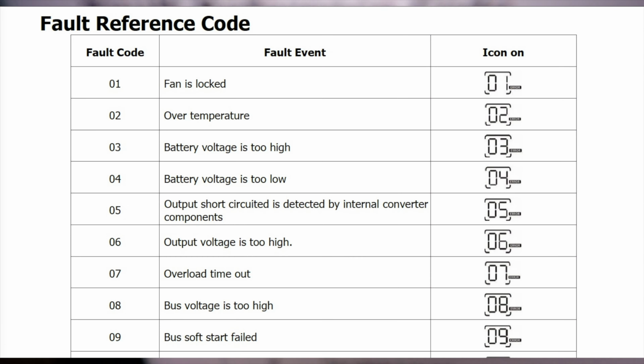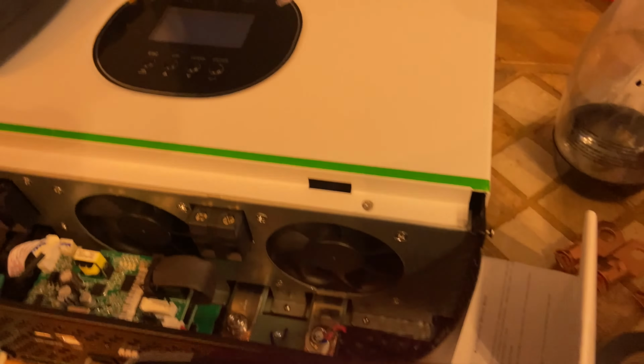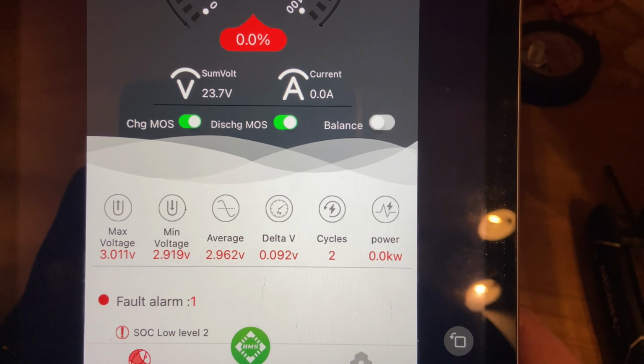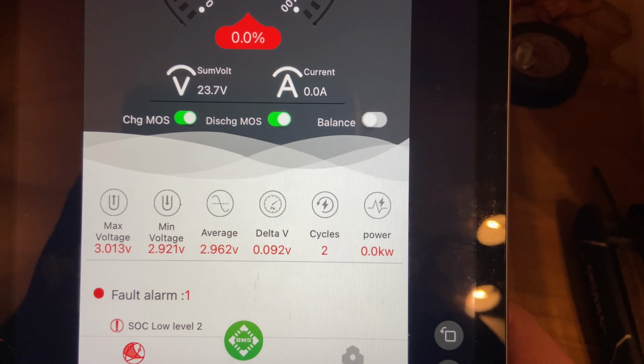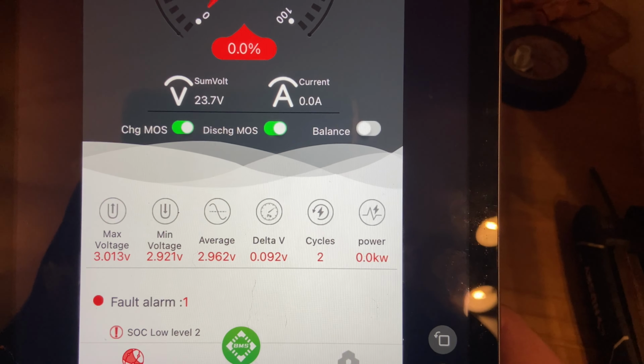Okay, I'll put that up on the screen - battery alarm voltage 4. So the inverter's off now, I shut it off manually, at 0 state of charge. The battery voltage is starting to come back up a little now that there's no load being drawn on the cells. We're at an average cell voltage of 2.962 and a sum voltage of 23.7.